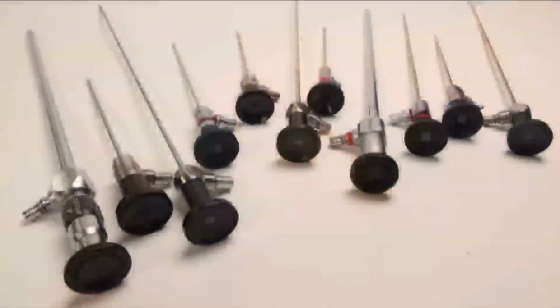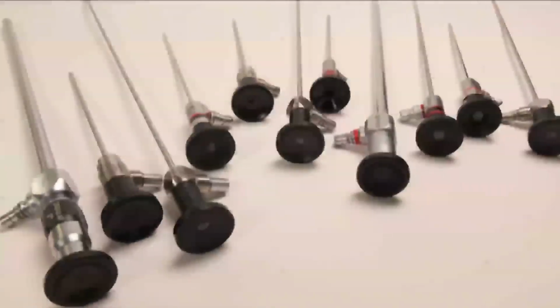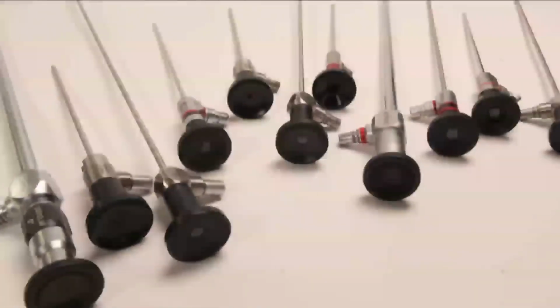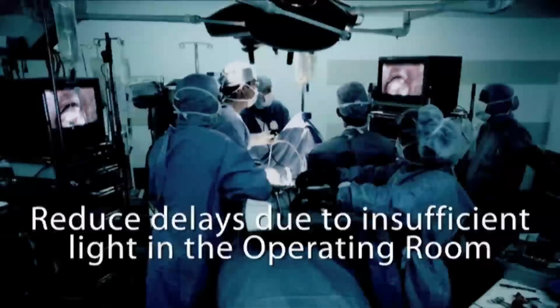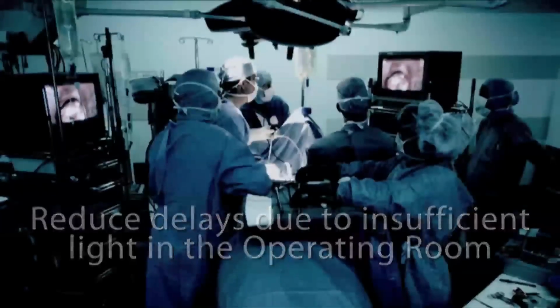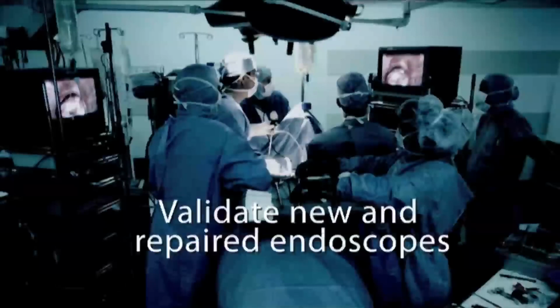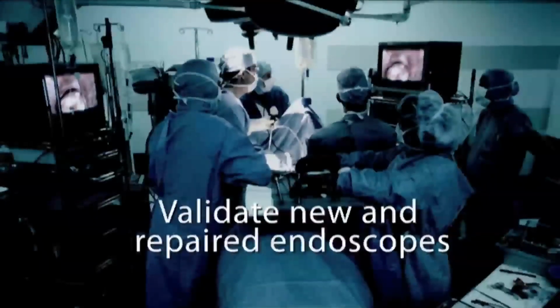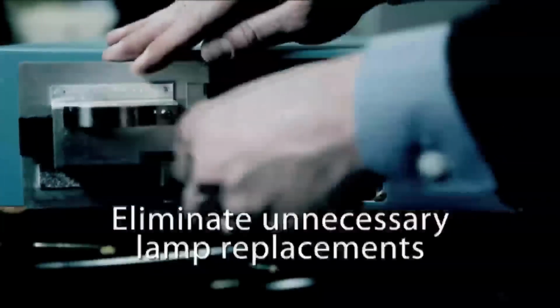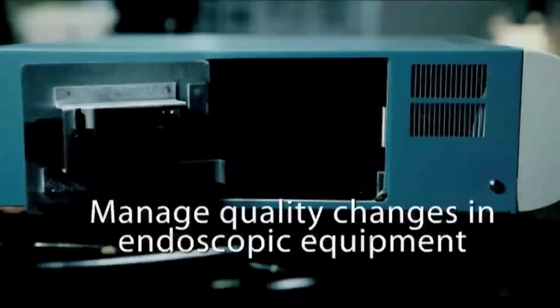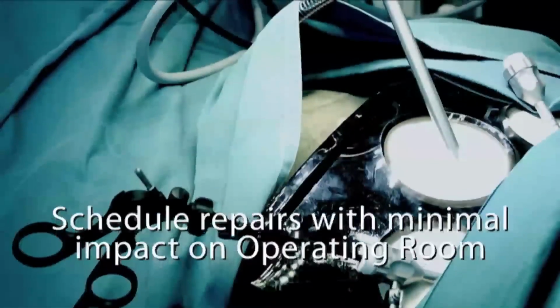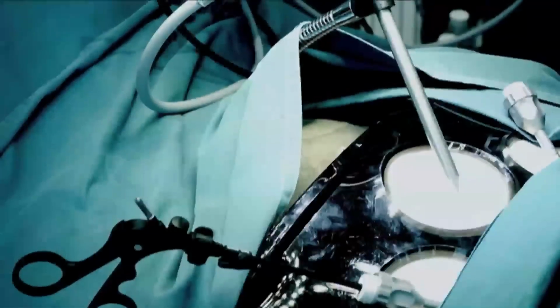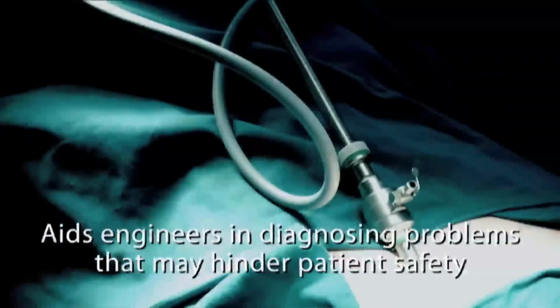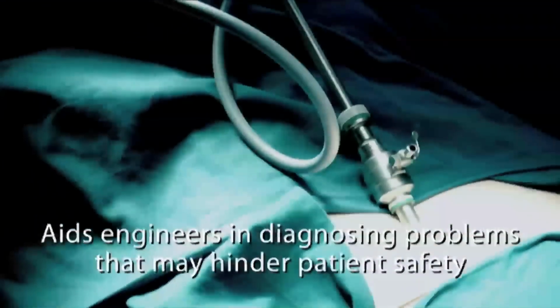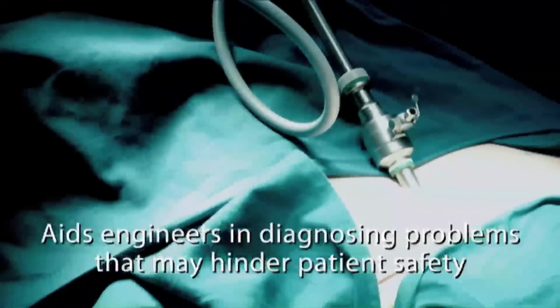Using a patent-pending optical bridge and integrating sphere assembly specially designed for endoscopic systems, biomedical engineers can reduce unnecessary OR delays due to insufficient illumination during endoscopic surgeries, validate new and refurbished endoscopes, eliminate unnecessary and expensive lamp replacements, verify equipment performance before and after repair, track equipment performance to schedule maintenance and repairs with minimal downtime, and help biomedical and clinical engineers identify problems before they become a burden on the OR schedule or impact patient safety.